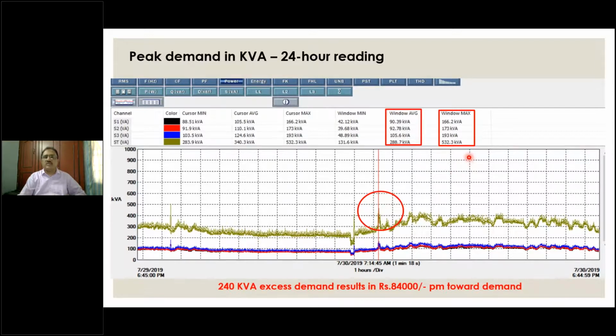So if they find a solution to start the chiller with a soft starter or a VFD, this peak will not register. This peak is what is causing them approximately 84,000 rupees loss. So this information is coming out of this particular one-day recording. Please remember, I'm continuously using the same one-day recording for different values and with different perceptions and interpretations.